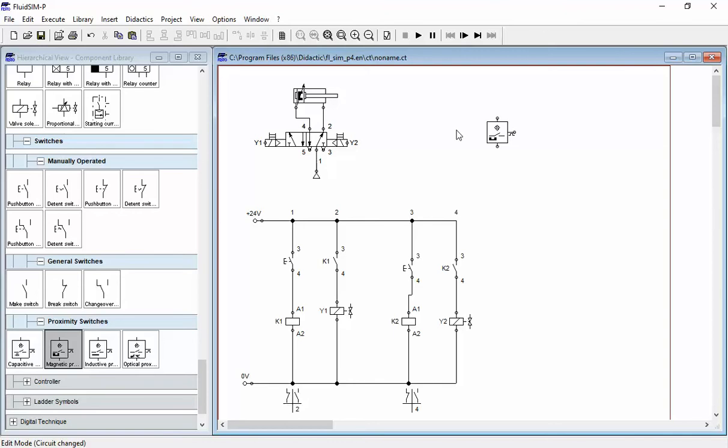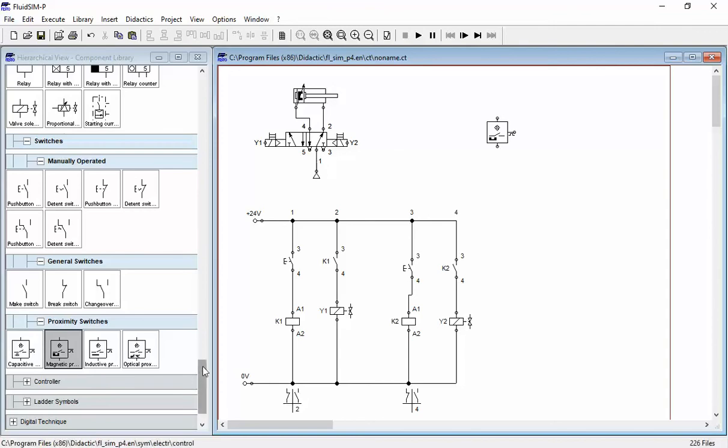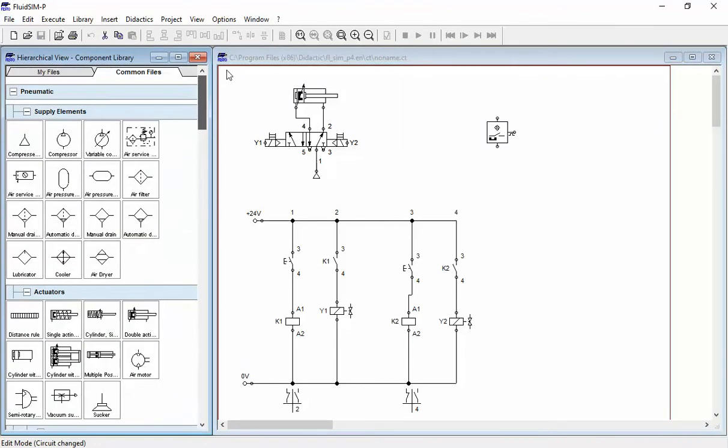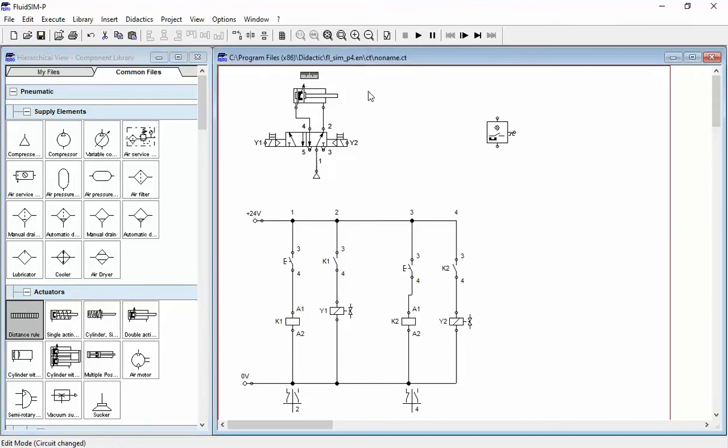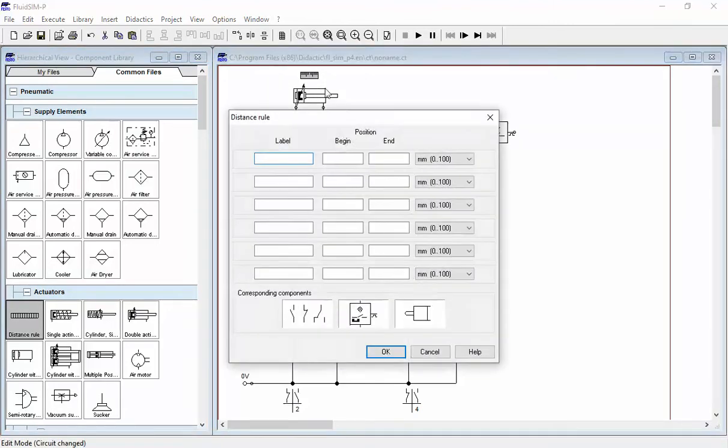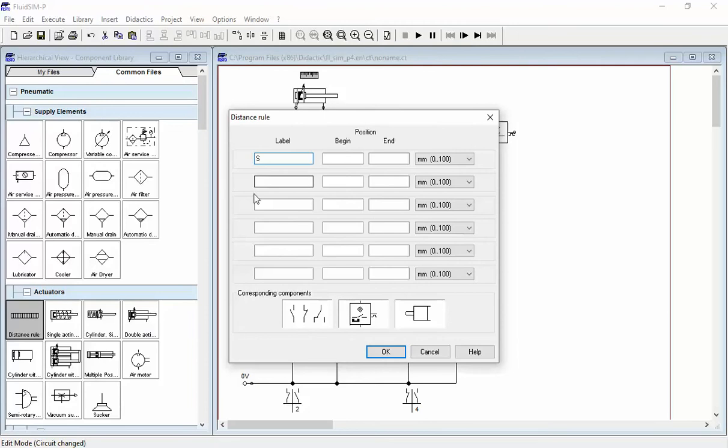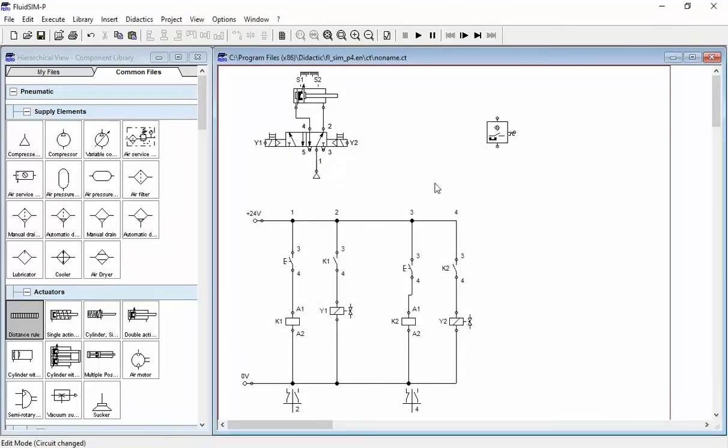How it works: this depends on the specific type of cylinder. The cylinder has to be suitable or matching with this type of sensor, because the piston of the cylinder has a magnet inside. I will mount S1 at position 0 and S2 at position 100. I can mount two sensors, S1 and S2, magnetic sensors. This magnetic sensor or reed switch we have to mount on the body of the cylinder.